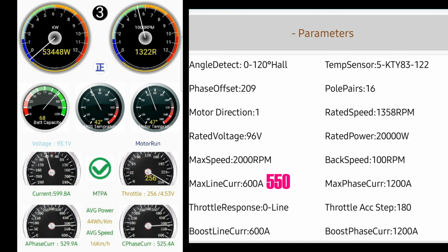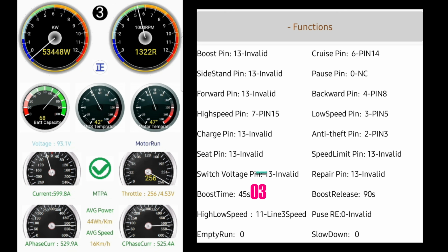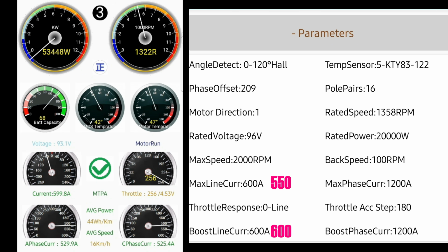Now the easy solution here, and this is where you want to use the boost switch, I could limit the line amps to 550 and I wouldn't sag, at least during this portion. When we get to the weak, we're probably going to see more sag, but for right now, I could limit it to 550, and then I could use a boost switch. I would have to see what my time is from 0 to 1000 RPM, and it's about 3 seconds. So I could set my boost switch to 600 amps for that 3 seconds. Hit the boost and take off on boost. Once the 3 seconds expires, it'll drop down to 550 amps. And that would be a good solution.